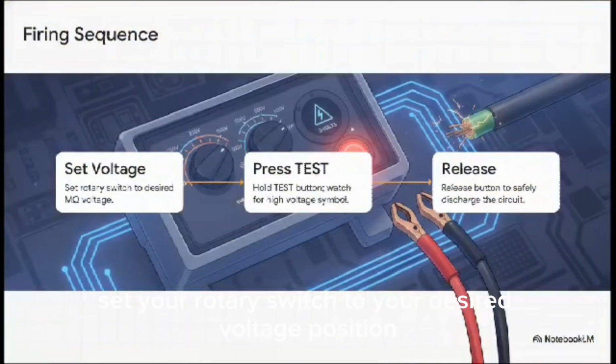First, set your rotary switch to your desired voltage position. Second, press and hold the test button. When you do that, you're going to see a flashing high voltage symbol pop up on the screen, and you'll see the actual test voltage being pushed right into the wire. Third, and this is key, when your reading is complete, you keep the leads firmly connected to the wire and then release the test button. This lets the circuit safely discharge itself back through the meter. Seriously, do not remove those leads until the display safely returns all the way back to 0 volts.